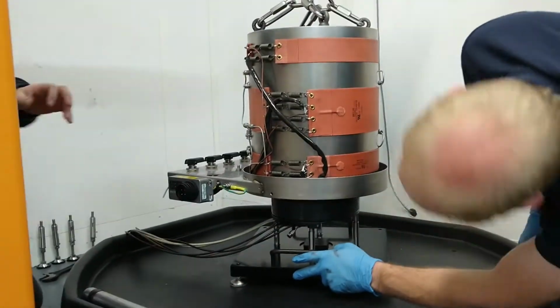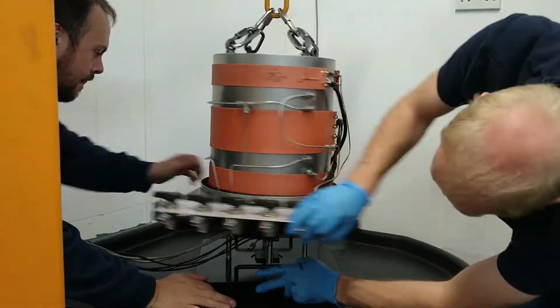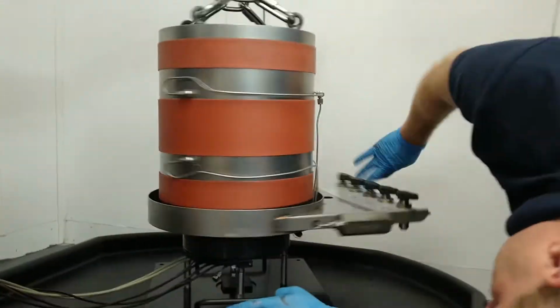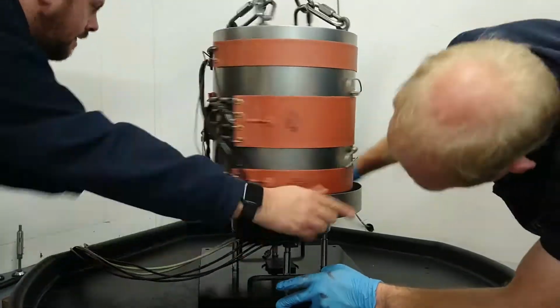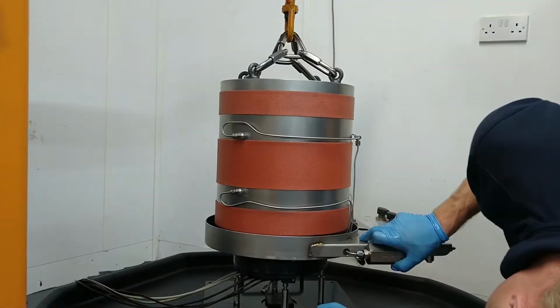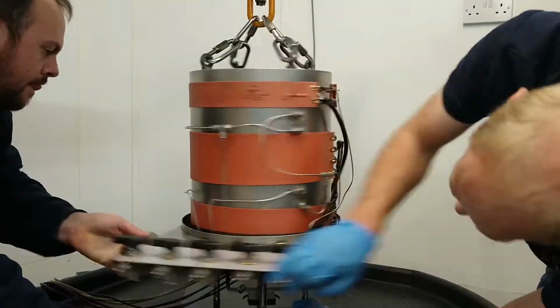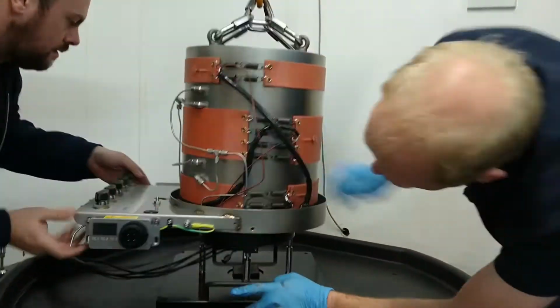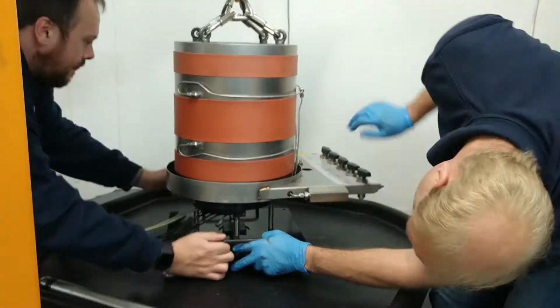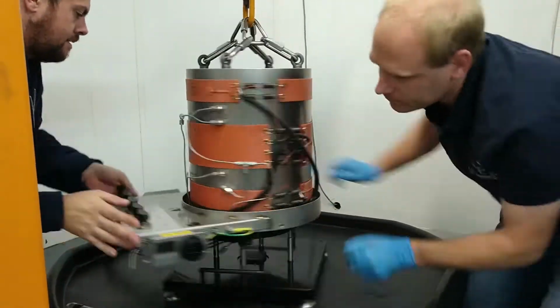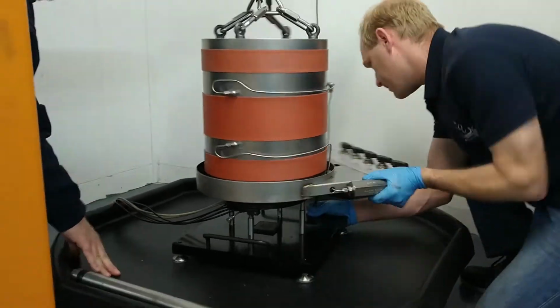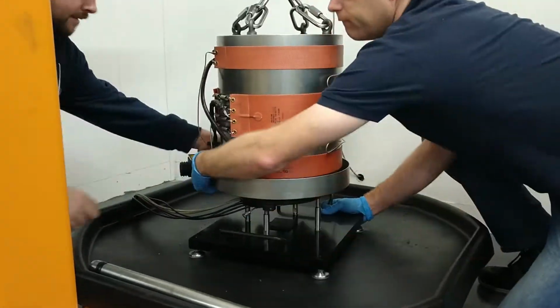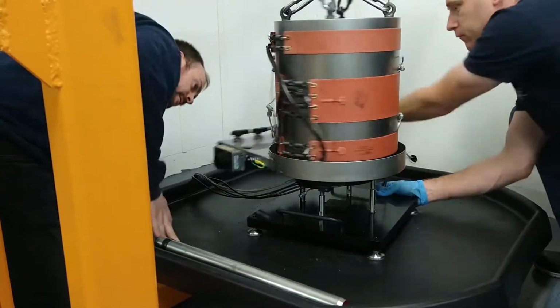Slowly start rotating the cell wall as it approaches the cell base. This will help align the threads. Do not lower too far, as the weight of the cell will sit on the upper thread, reducing the ability to smoothly rotate the cell wall. The lifting device should always be taking the weight of the cell during the fitting process. Looking from the side, it is important to monitor the depth of the assembly jig pins.